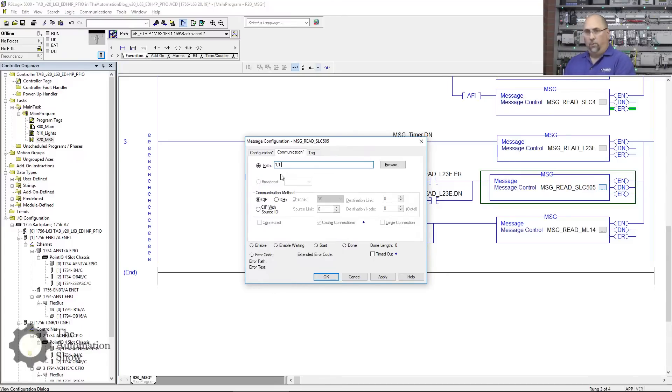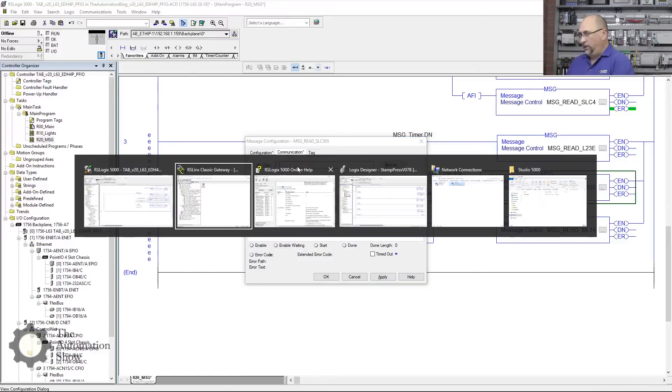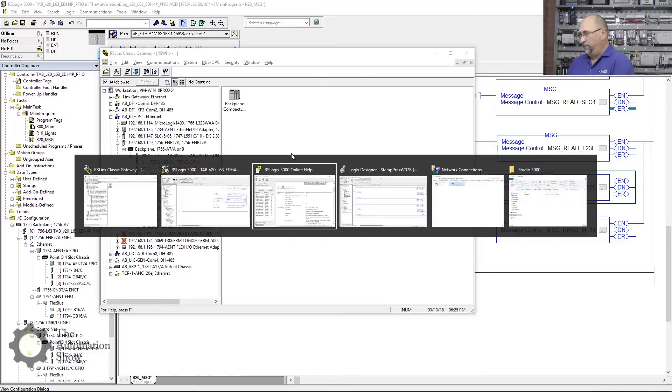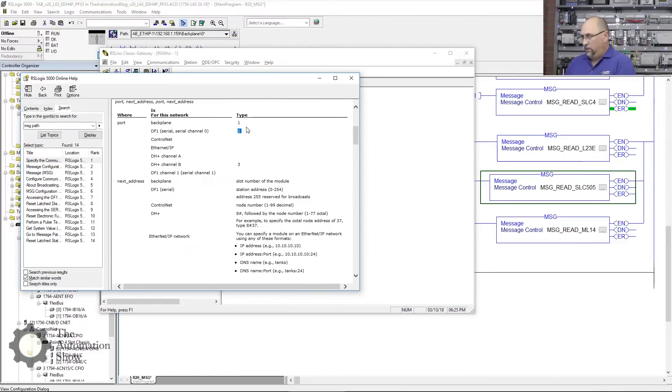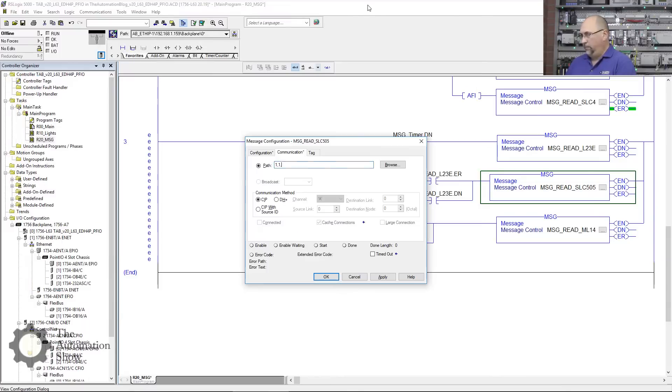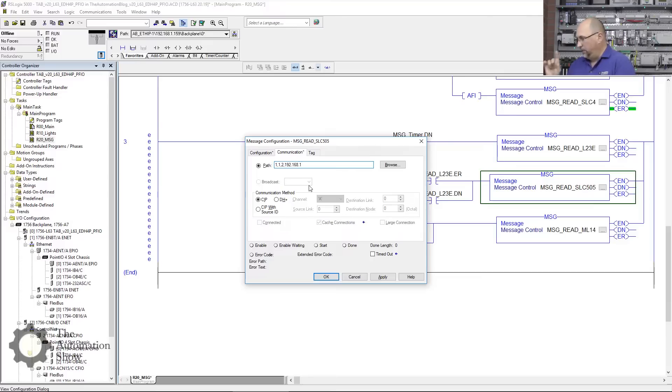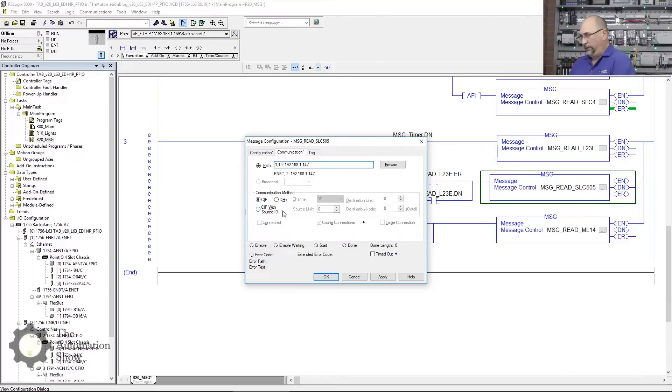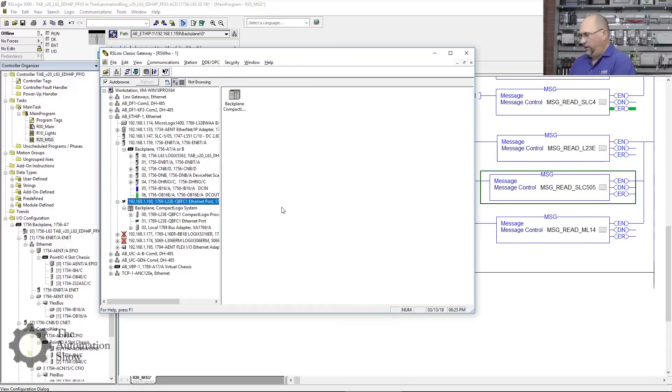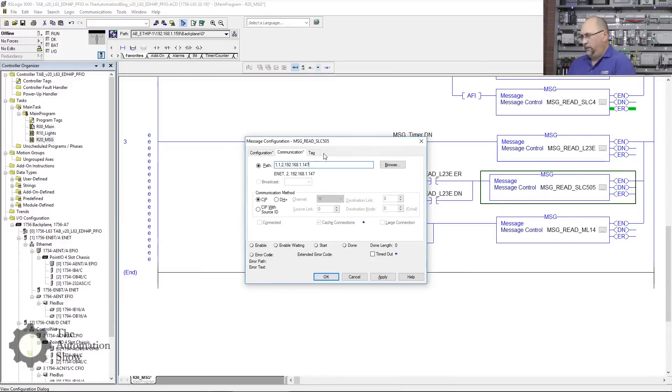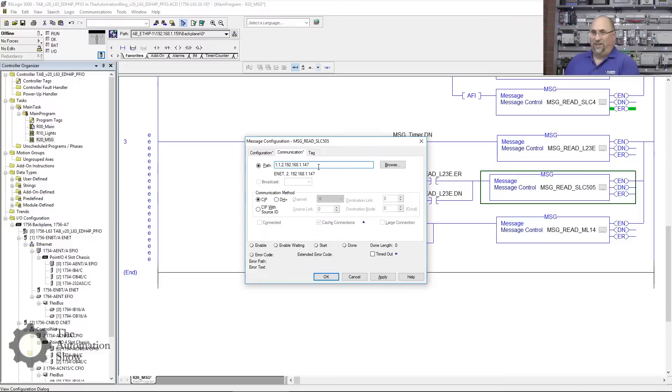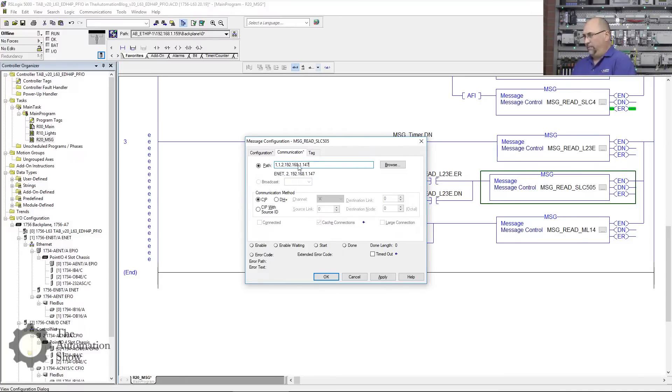Now we got our communications. Again, it'll be 1 for the backplane, 1 for slot one, and then I think it's 2 for the Ethernet IP. And then the IP address 192.168.1—we're talking about the SLC right? That's .147. We can see that right here, there it is. I think that's it. There's no chassis like with the Compact Logix inside the SLC 500, so we'll leave it like that and click Apply and OK.